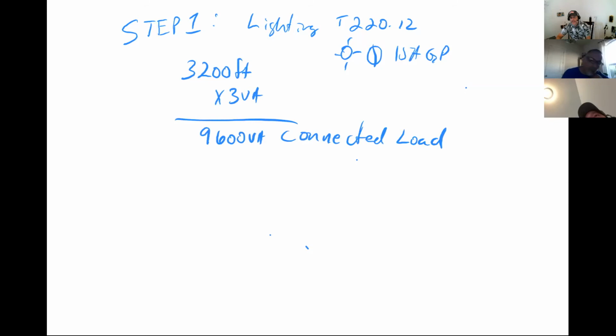Because generally speaking, economics is going to make it be the minimum, whatever is required, right? And it's based off of that 6 foot. So if you go up by square footage, you're going to increase the wall space. You're going to have a couple more receptacles. So it's kind of built into the number, right? And it just saves us a step. So that's step 1. Now, I want to point out that's a connected load. That's not what I would use to actually calculate the feeders, because that typically means that all the lights would be on at one time, right? In a residential dwelling, that didn't ever happen, except in my house. You see my kids. Yeah, I was just about to say, you stole my punchline.